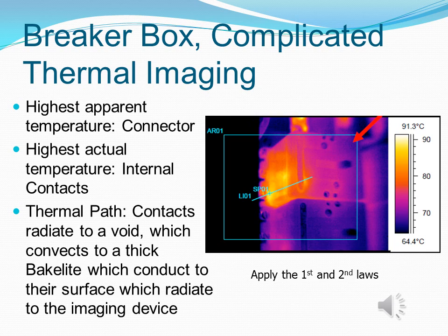Okay, but think about how the heat comes to your imaging device to make the image that you're looking at. Okay, it's apparent heat, right? So how did it get there, and how is that complicated? In this case, it is made by high resistance internal contacts inside the device and wicking out to the contact that you see at the outside of the device to the left.